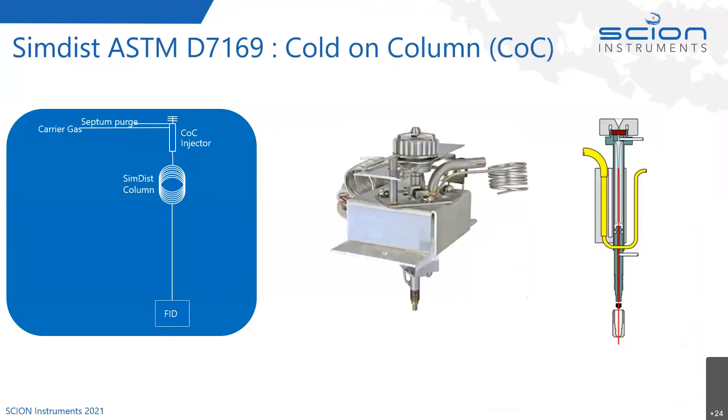The injector used is a cold on-column injector. There's no split involved and no split line fitted — it's just a very simple capillary on-column injector. We're using a megabore column, and you can fit 0.53 ID columns. Looking at the cross section, there's a yellow cooling pipe that can carry liquid CO2 or liquid nitrogen, with liquid CO2 being most popular. It also has a heater cartridge on the side. It's very small and compact, with a very short nozzle that goes into the GC column area, so there are no cold spots.